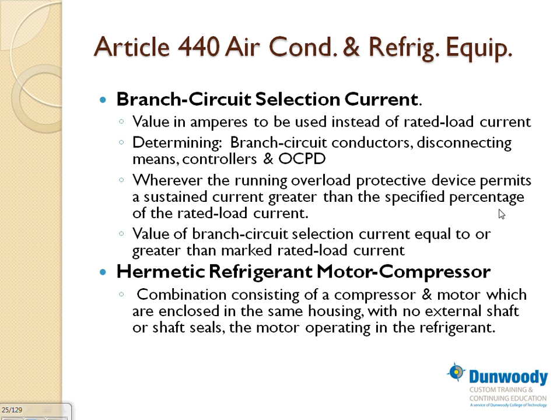So when you design your branch circuits, overcurrent protection device, disconnect and controller, you're going to use either the rated load amps of the equipment or the branch circuit selection current. Either way, it's going to be on the nameplate. You're going to use the branch circuit current or the rated load, whichever is larger. If the branch circuit says 100 and the rated load amps on the equipment say 120, you'll use 120 and size your equipment at 120. So basically, the branch circuit selection current is equal to or greater than the rated load amps.